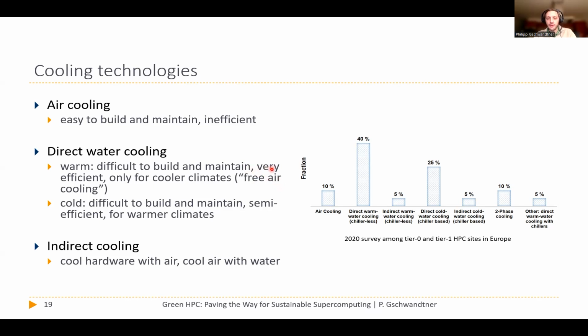This makes it very efficient, but it's only suitable for cold climates, something you can easily do if you build a data center in Scandinavia, for example. If you go to Southern Europe, you sometimes need to actively cool the water down. This is where cold water cooling comes in, which is not as efficient because you have active chillers on the roof that work like a heat pump, like your refrigerator, to actively cool the water down, which takes electricity and energy to pull the heat away from the water.